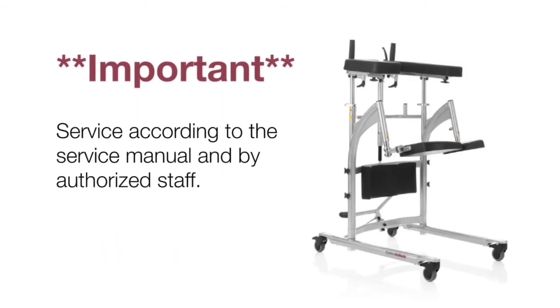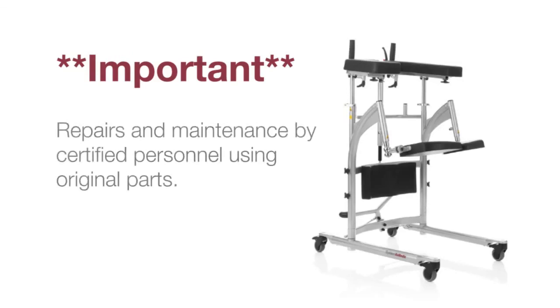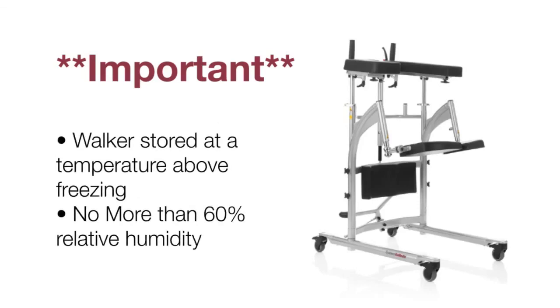The RoWalker 400 should be thoroughly inspected and serviced when needed, at least once per year. Perform complete weight tests and pay particular attention to the parts that show wear, such as joints, bolts, welds, wheels, etc. Service must be carried out according to the Handicare service manual and by authorized staff. Repairs and maintenance may only be done by trained and certified personnel using original parts. When storing, keep the walker at a temperature above freezing and relative humidity no more than 60%.